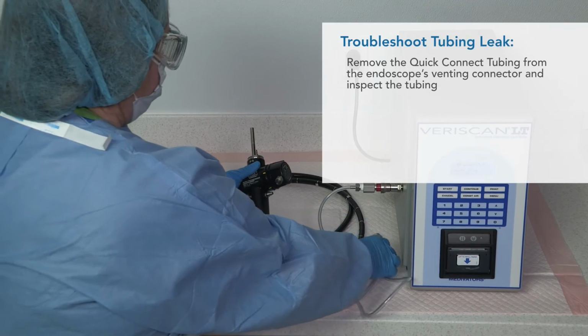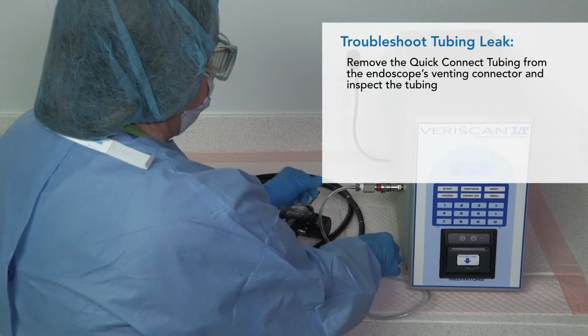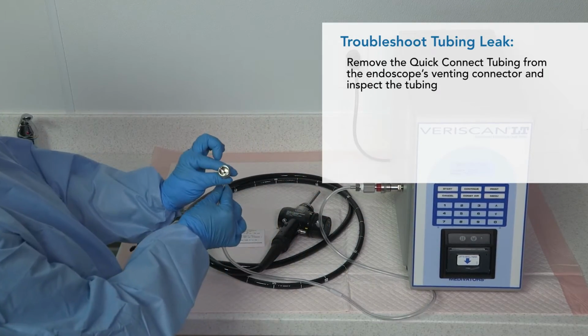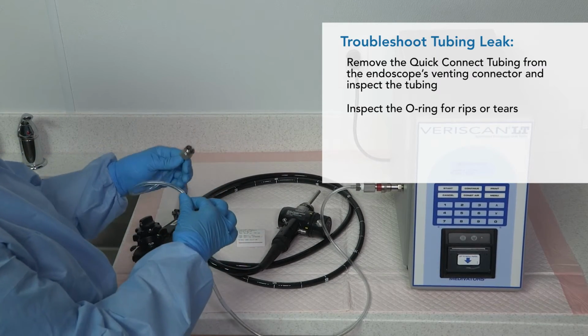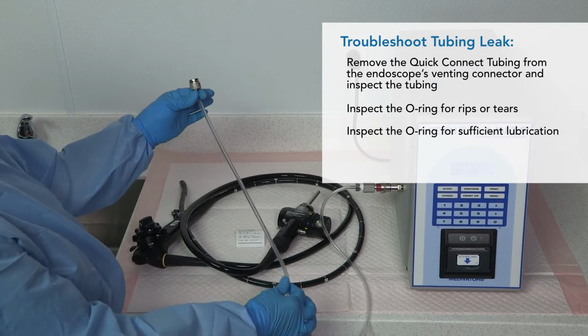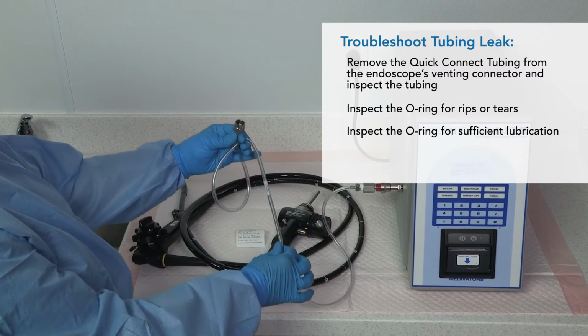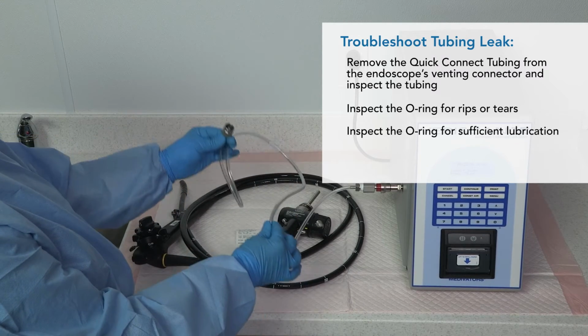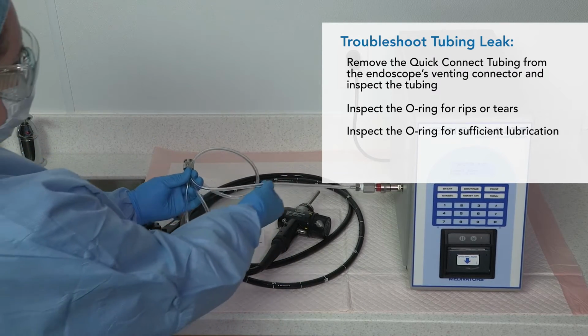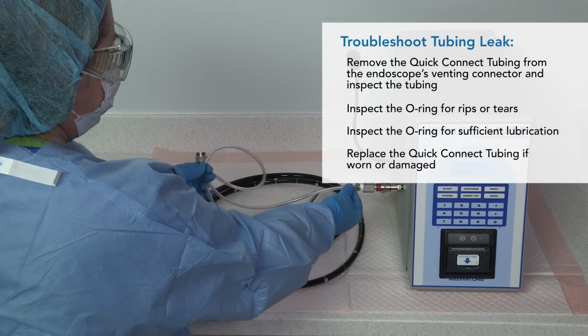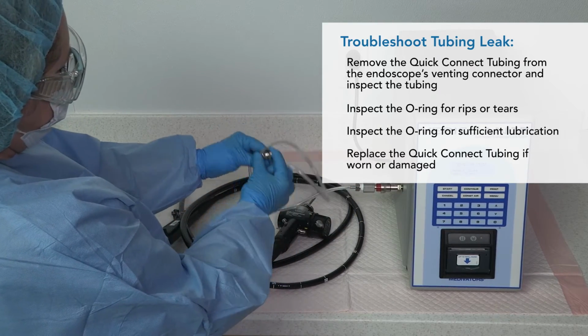First, remove the Quick Connect tubing from the endoscope's venting connector and inspect the tubing for wear, damage, or holes. Inspect the O-ring for rips or tears. Inspect the O-ring for sufficient lubrication. The O-ring can tear if dry. Lubricate weekly or more if dry. Replace the Quick Connect tubing if worn or damaged.